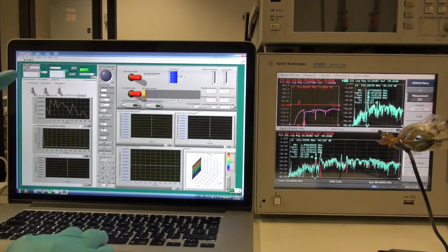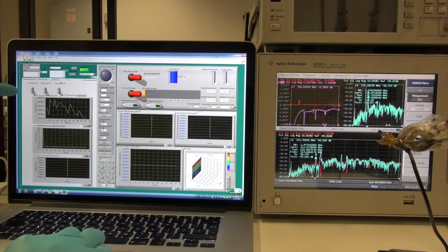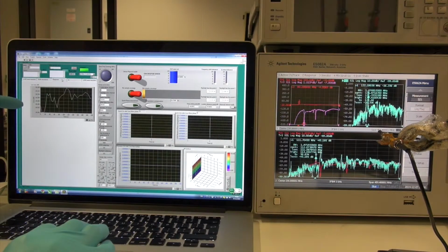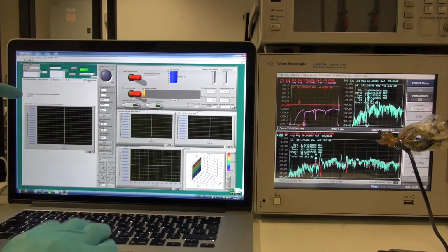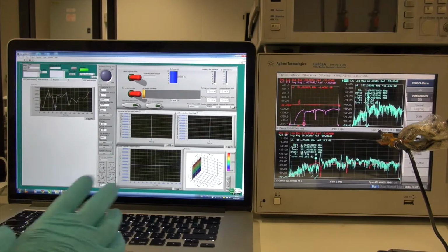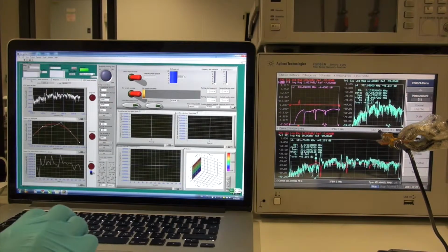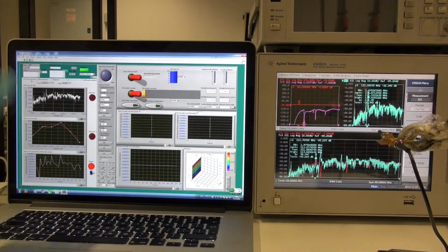And also from this module, we can switch on and off the data fitting, data saving to the local computer, and control the different displays, and give the detailed analysis for both the frequency drift and, for example here, the phase drift. We can also manually measure the quality factor of the device, which is for diagnosing the device quality. So this is for the data fitting, data acquisition and data monitoring.